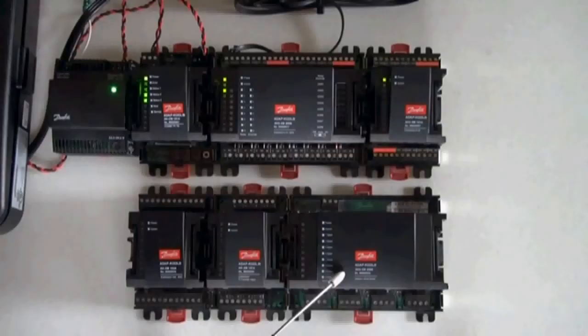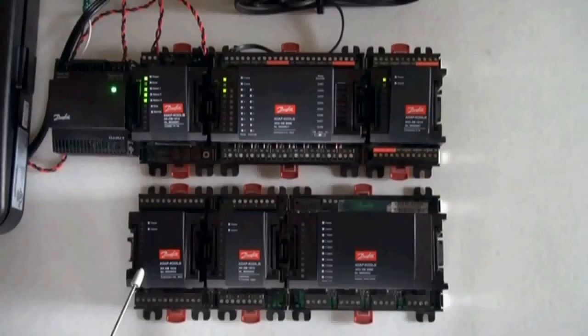Next, you'll see the Danfoss stepper board. This stepper module can drive 4 stepper valves. This is a pulse module used to read up to 8 pulse inputs, typically from kW meters. And lastly, this module reads 4 analog inputs or 4 digital inputs at the top and provides 4 analog outputs at the bottom.